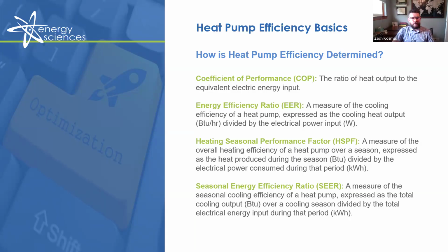Next, we have heating seasonal performance factor, or HSPF. This is a measure of the overall heating efficiency of a heat pump over a season. This is expressed by the heat produced during that season in BTUs, divided by the electrical power consumed during that period in kilowatt hours. HSPF is often regarded as the average COP over an entire heating season. So for example, an HSPF of about 6.8 would be comparable to an average COP of 2, okay?